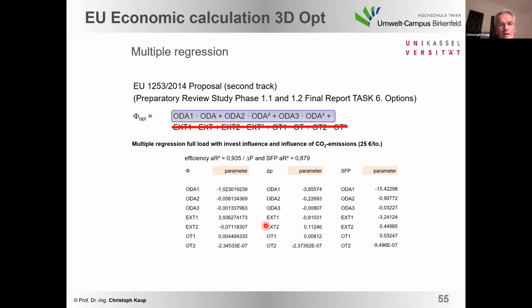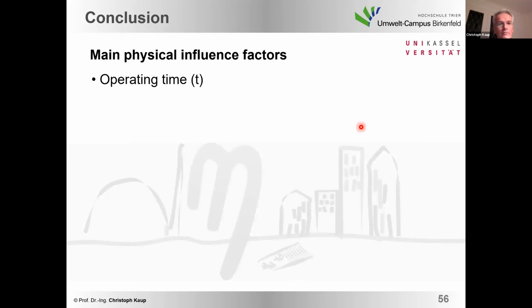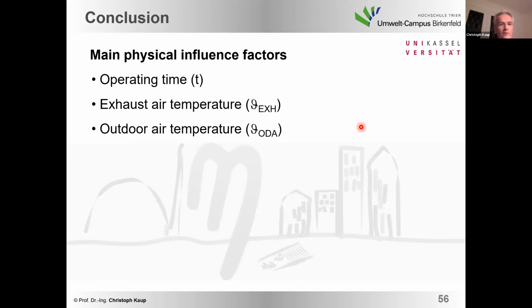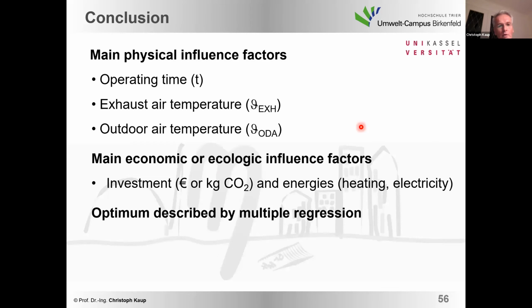Unfortunately, the European Commission in their draft neglected the extract air temperature. Okay, that might be a possibility, to set it as a constant value. But from my point of view, I think it's a big mistake to neglect the operating time, because the operating time has the same influence factor, as you already saw, as the outdoor air temperature. So the influence factors, as already shown, are operating time, exhaust air temperature, and outdoor air temperature, and also the investment and energy costs.